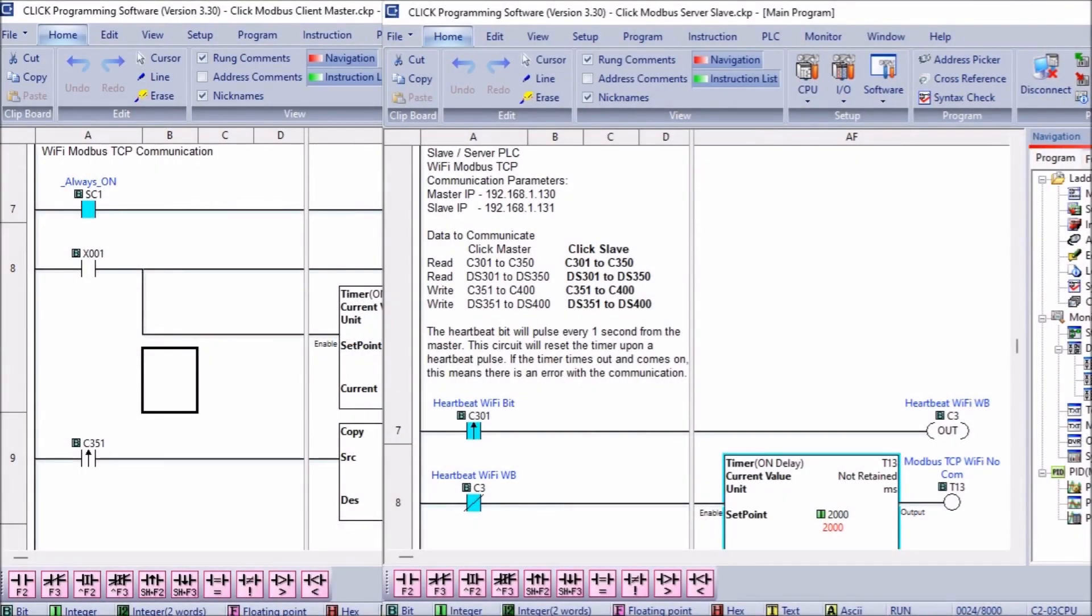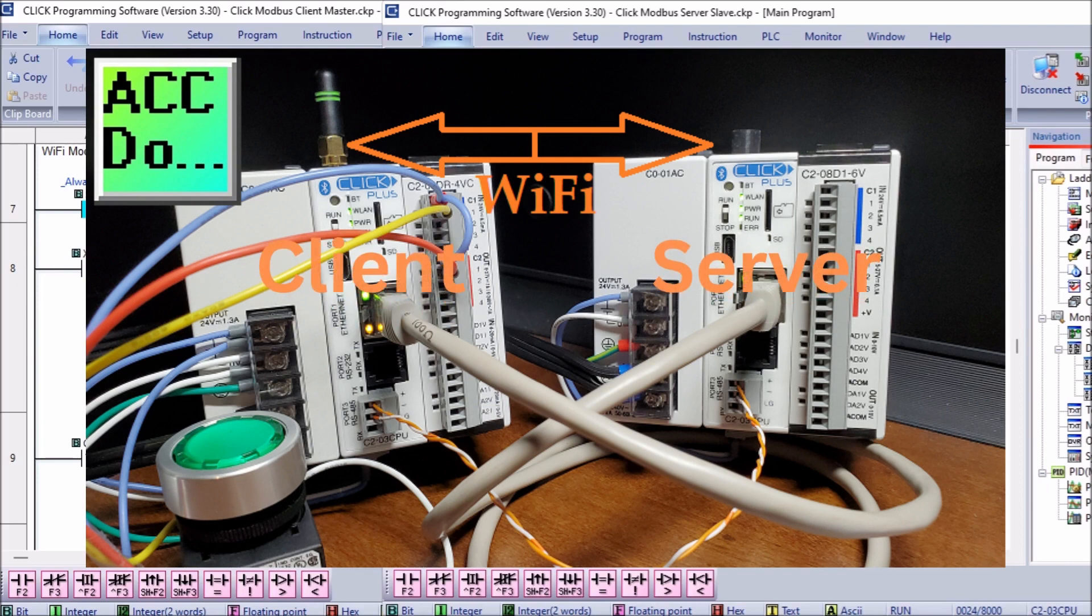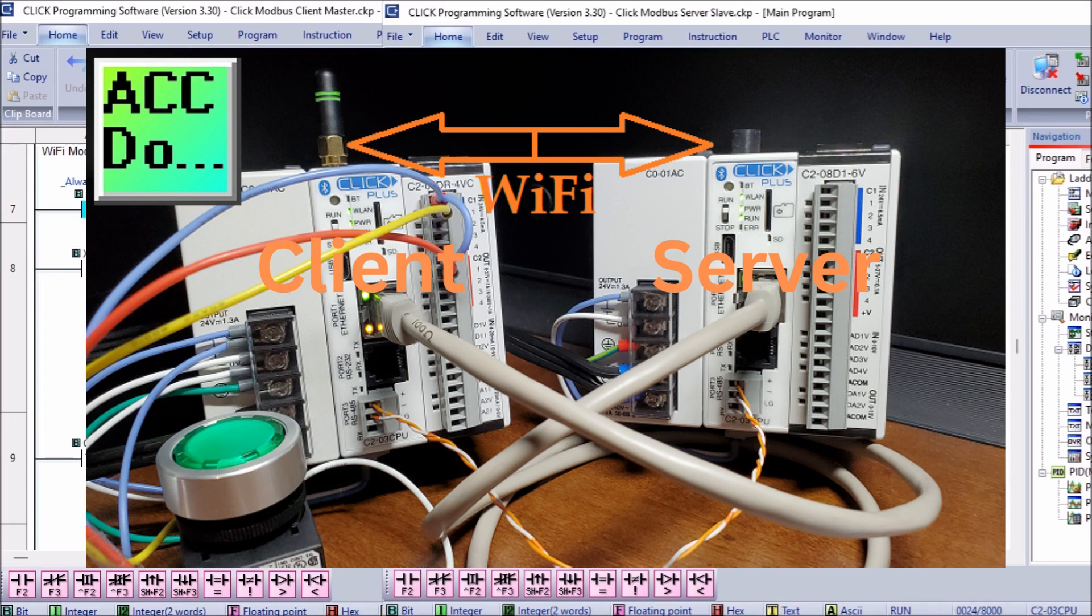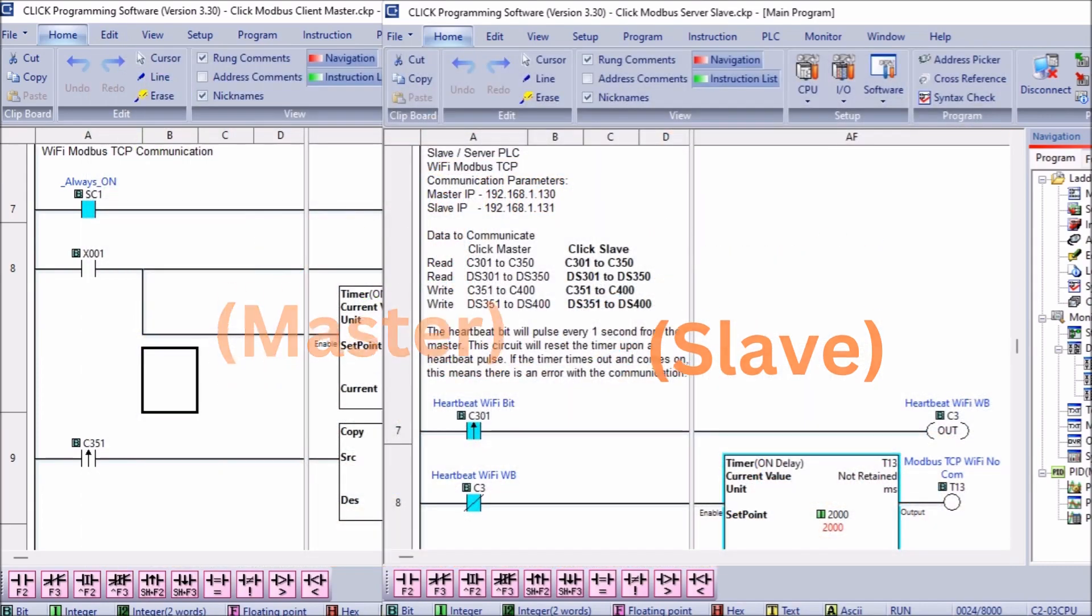The Click Wi-Fi connection is wireless. A static IP address must be set for the client as well as all the servers. In Modbus TCP communication, the controller sending the command is called the client. The server controller will respond to the commands from the client. In Modbus RTU or serial, the client is referred to as the master and the server is the slave. An easy way to remember this is the two S's: Server, Slave.